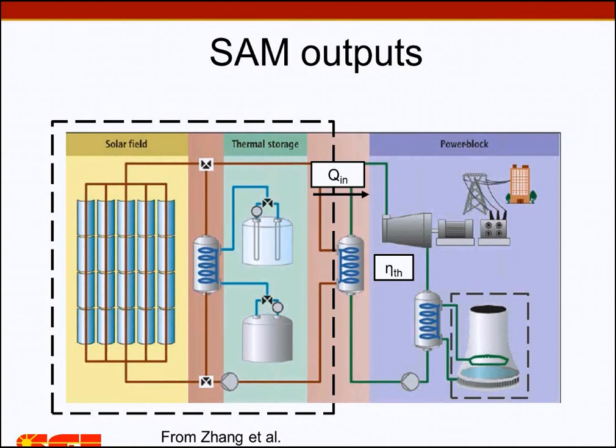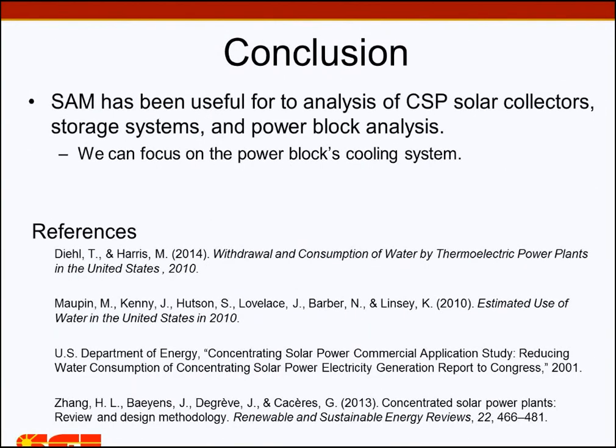This gives me an hourly profile for the week I was looking at of the heat rejection required. For that peak July week, the hourly results show that this 35 megawatt power plant at peak, with a solar multiple of two, has a rejected heat average of about 58 megawatts, with a little variance throughout the day based on how it's dispatched. This covers the 168 hours I looked at.